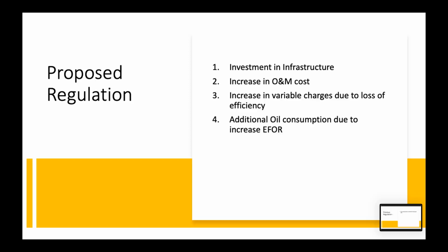The next is the increase in the variable charges due to decrease of efficiency. This has been considered on two grounds: one is the heat rate, the other is the APC part. Next is the increase in oil consumption due to increased equipment forced outage rate, because many times during cycling the equipment may go out and the unit has to take oil, so its oil consumption may increase beyond the specific norm of 0.5. So all these things have been taken care of in these regulations.